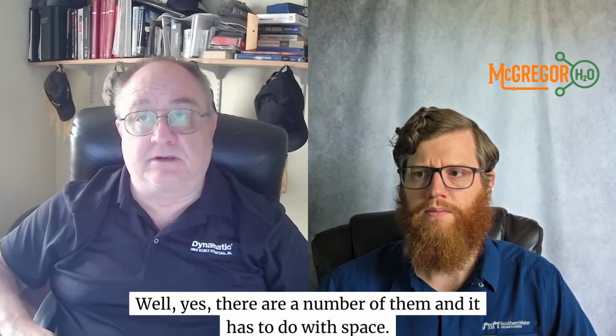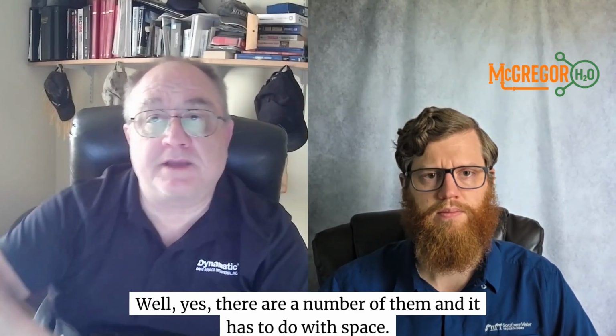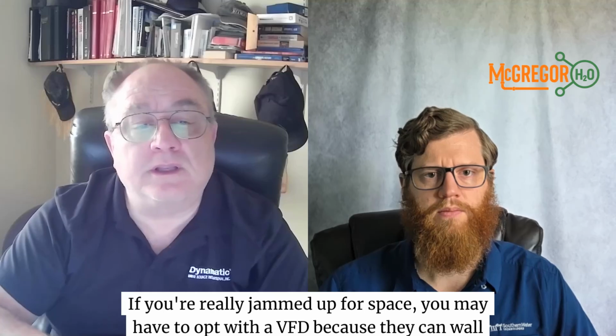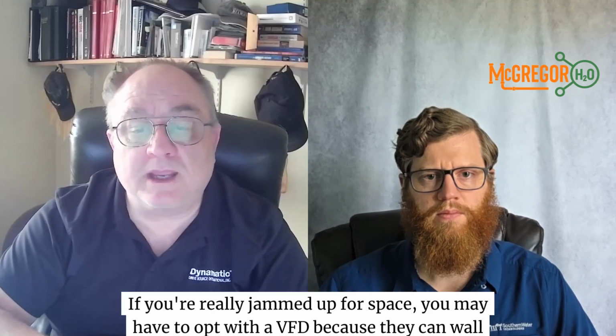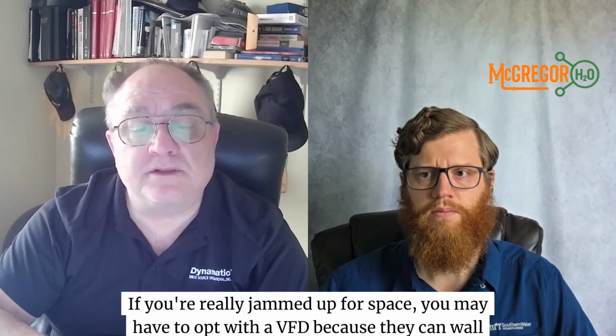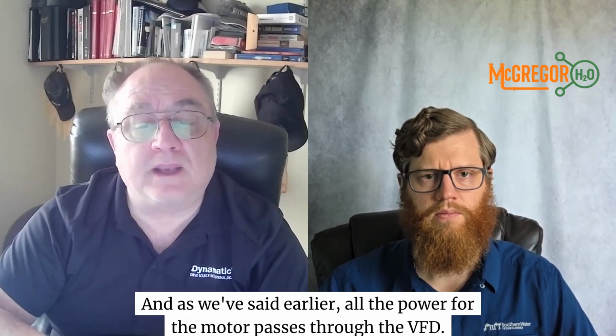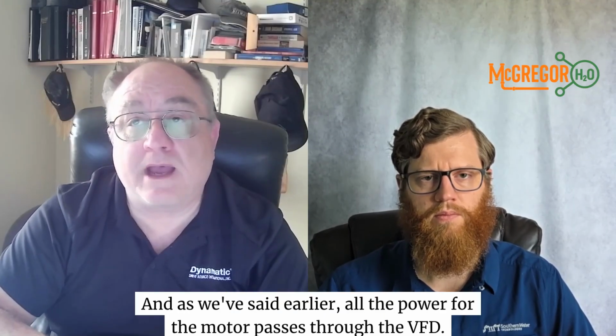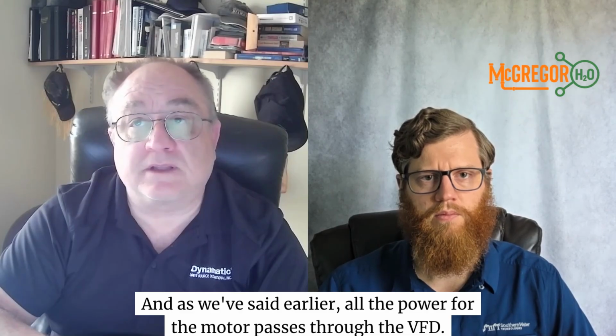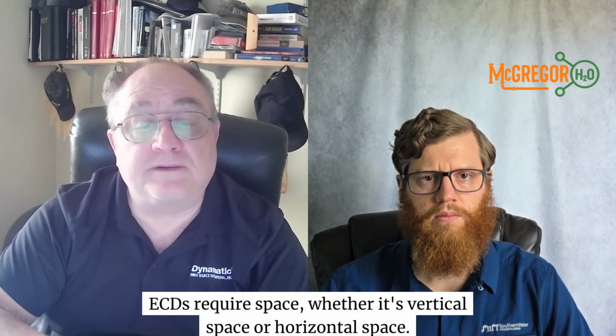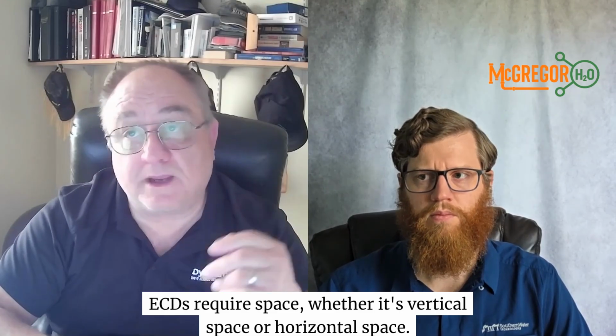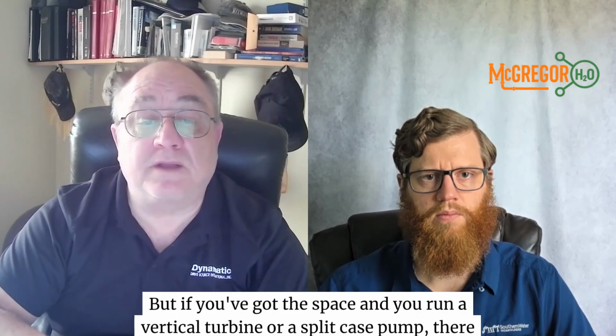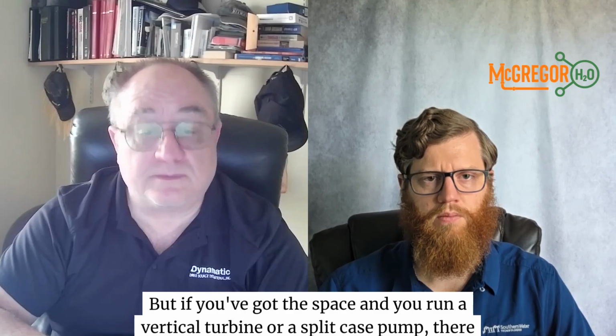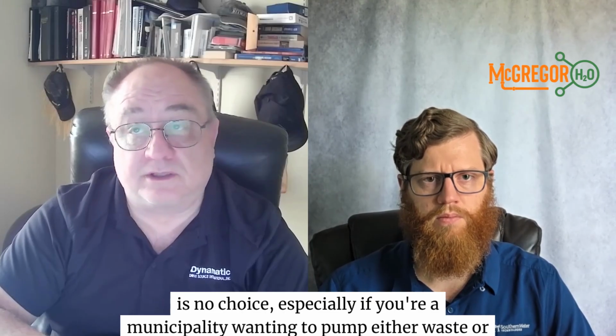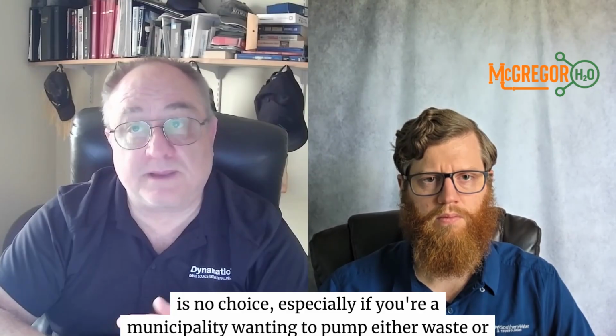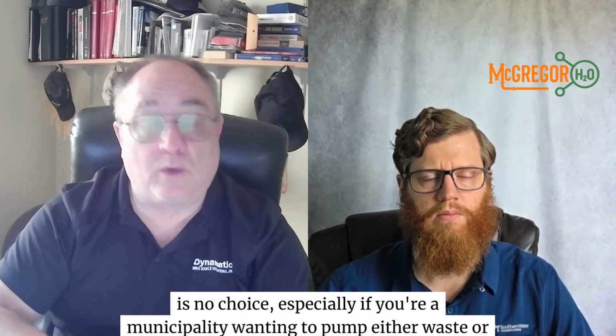Well, yes, there are a number of them, and it has to do with space. If you're really jammed up for space, you may have to opt with a VFD because they can wall mount those things. And that, as we said earlier, all the power for the motor passes through the VFD, so that is one advantage for them. ECDs require space, whether it's vertical space or horizontal space. But if you've got the space and you're running a vertical turbine or a split case pump, there is no choice, especially if you're a municipality wanting to pump either waste or fresh water.